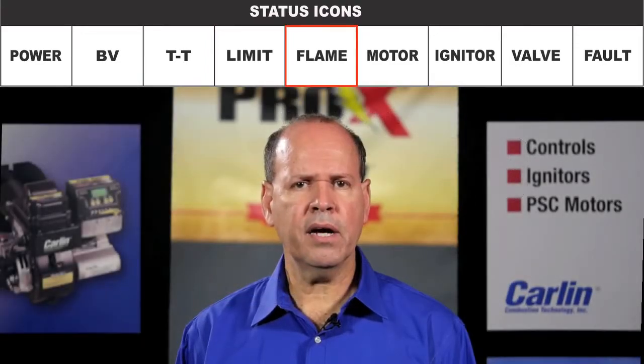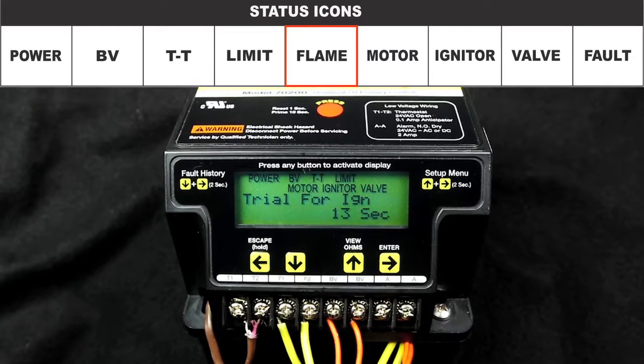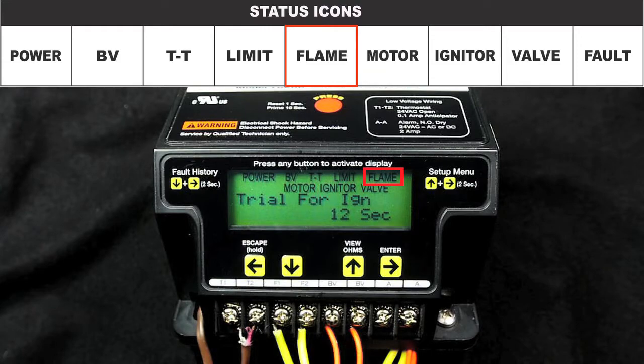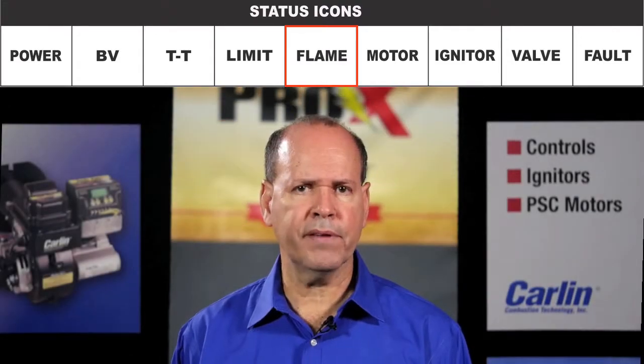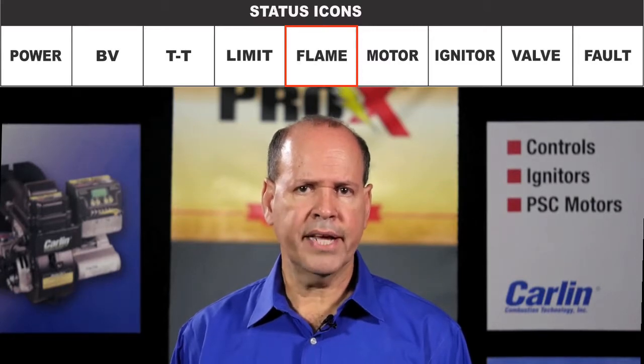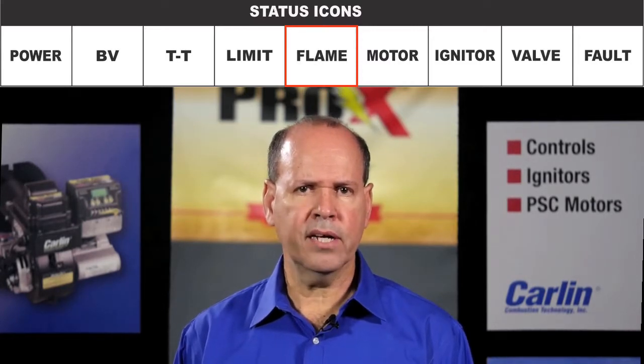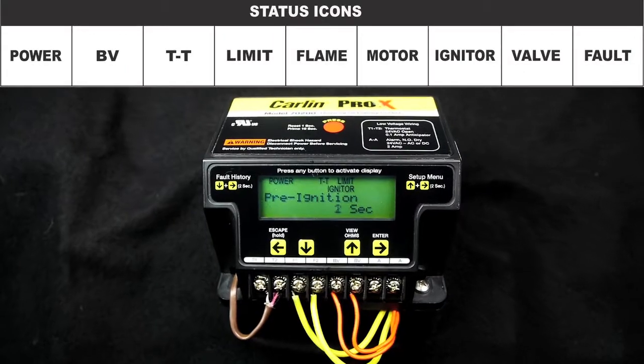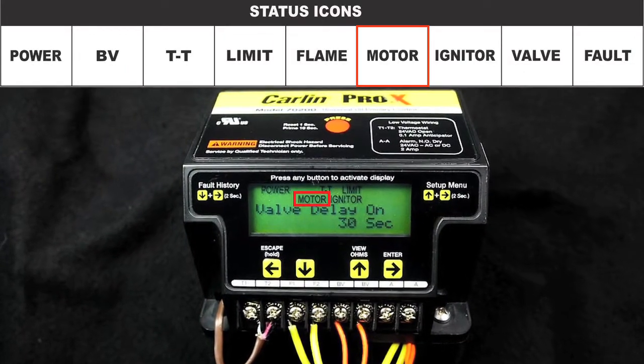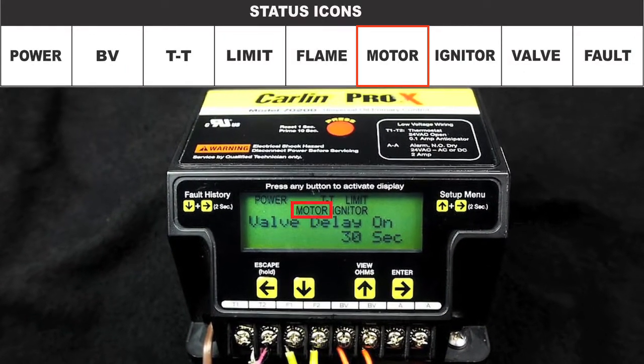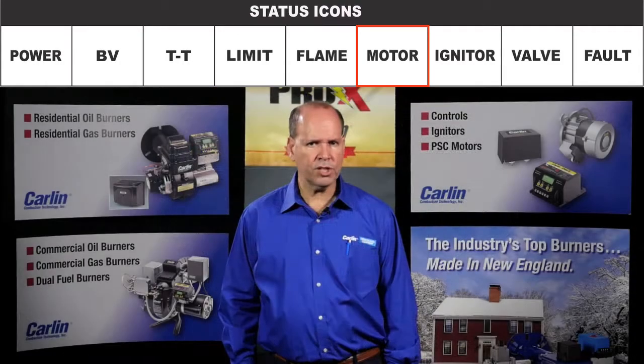The flame icon is present whenever the CAD cell detects a flame. A flashing flame icon indicates a high ohm value in the flame detection circuit. Attention to the flame or CAD cell is necessary. The motor icon indicates that the motor is energized. Likewise, if the motor icon flashes, that means the motor was not detected or may be faulty.